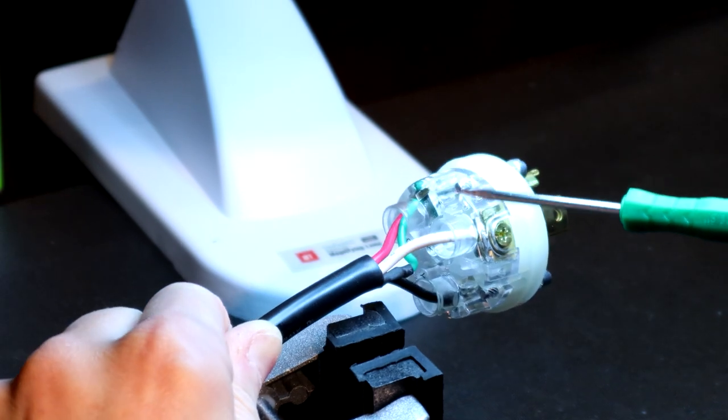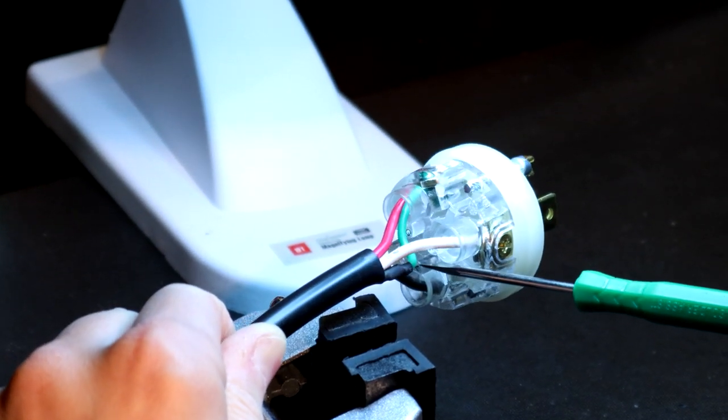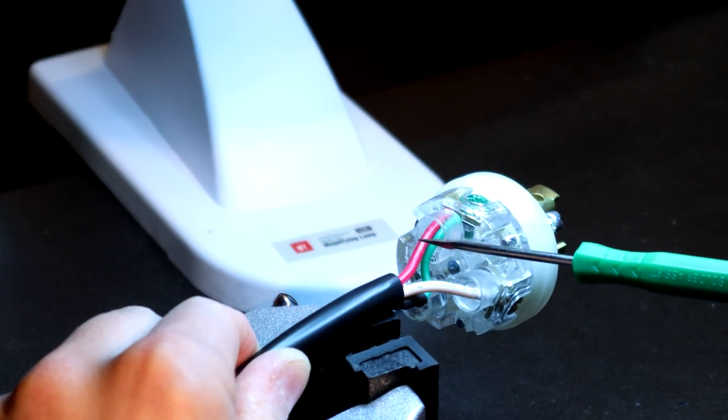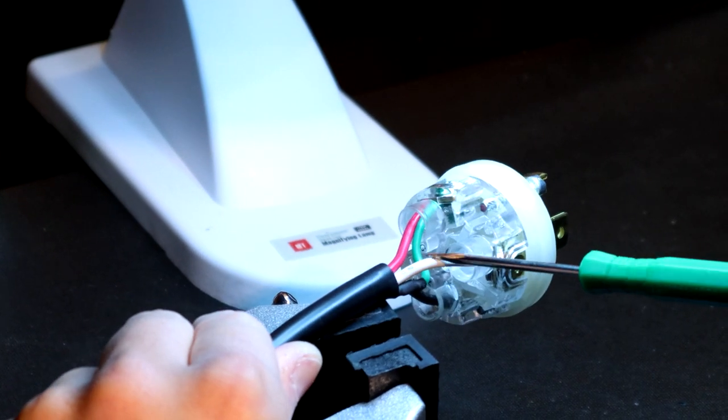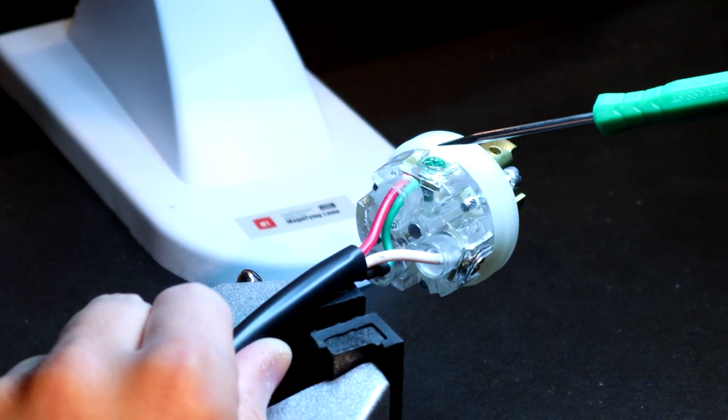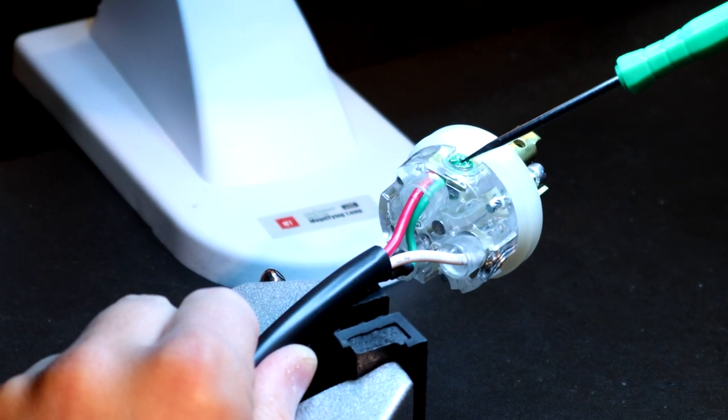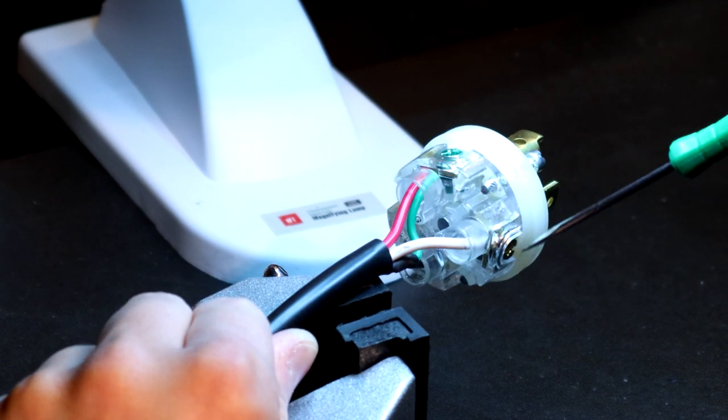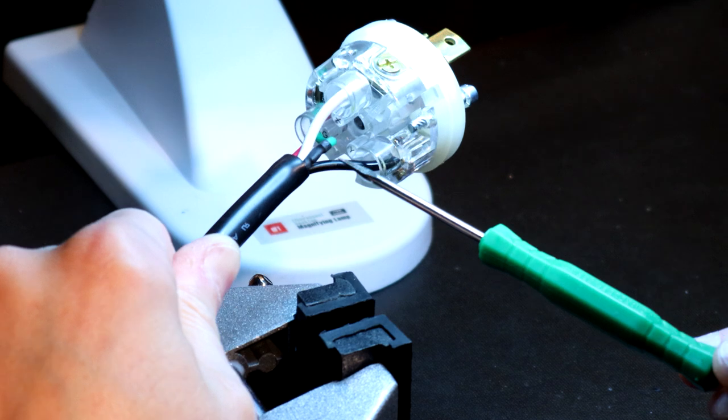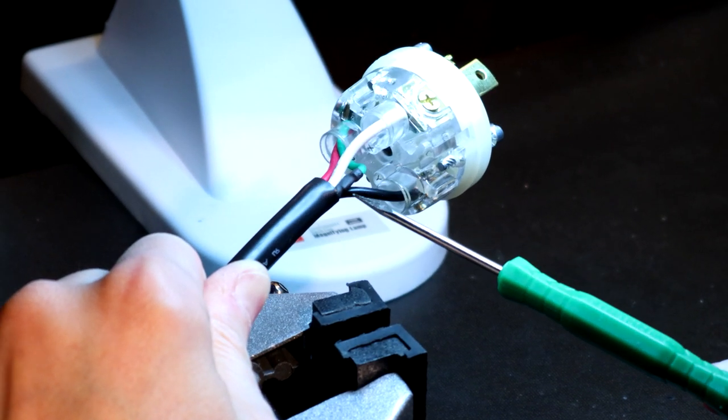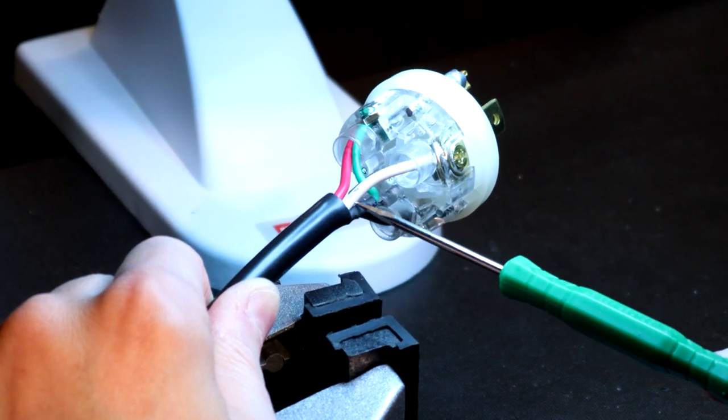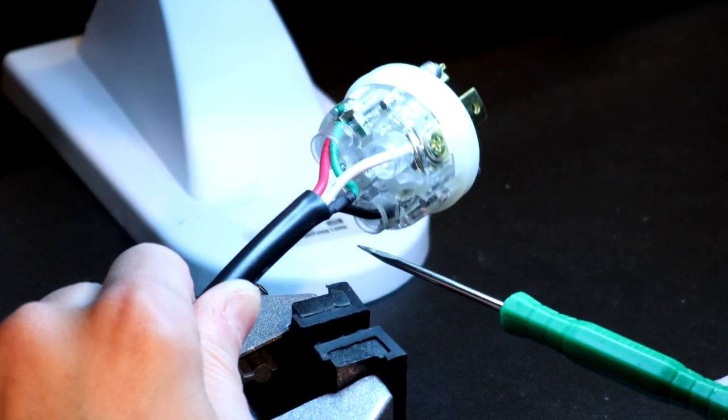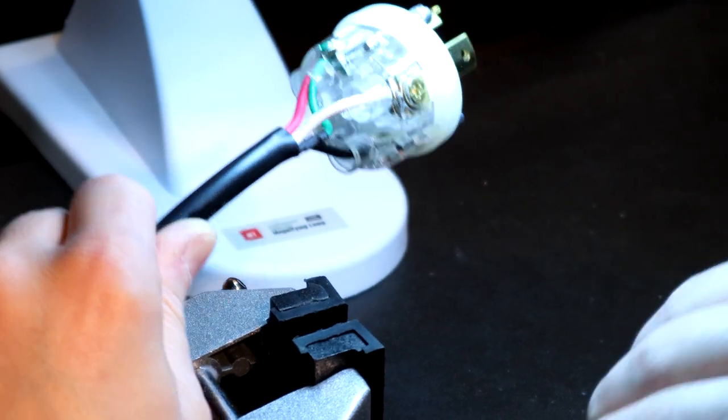You also see that secondary lead coming in and that is our shield drain. You can see why I prefer to use silicone leads. You can see how it comes in, comes over and it is soldered to this actual lead right here. All of these leads have soldered tinned ends. That's so that once you insert them inside these terminals, you know that once you cinch it down, it's going to be properly done. You can also see the insulator used on the ground drain as you should be using to protect. God forbid, if any of these ever deteriorated, you would never want a dead short. That always absolutely isolates that.